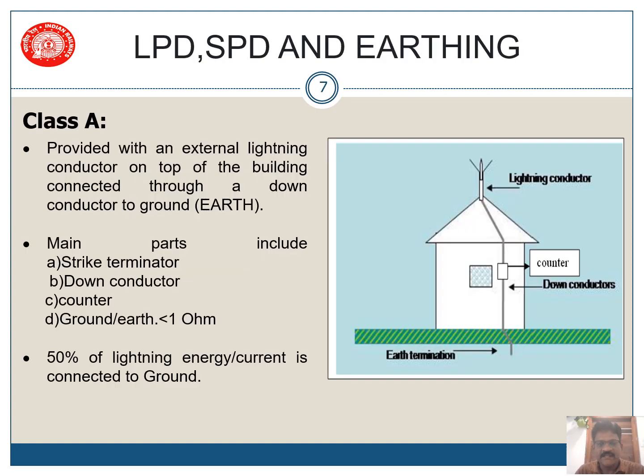Going further, here you can see the Class A protection. This is the building, our signaling system or relay room, where you have a protection. This Class A protection is generally provided for the whole building. If the building is big, we need to provide more Class A protections. Whenever lightning strikes, almost 50% of the current goes this way to earth, and there is even a counter provided.